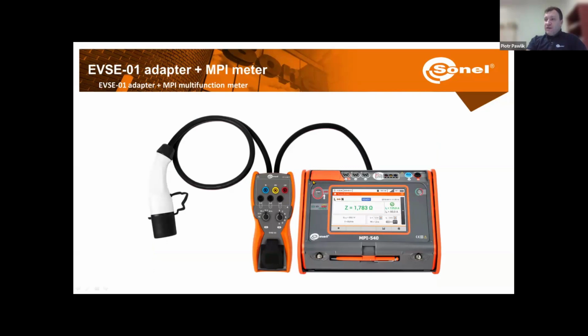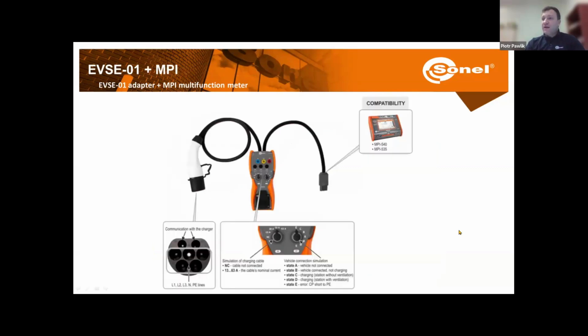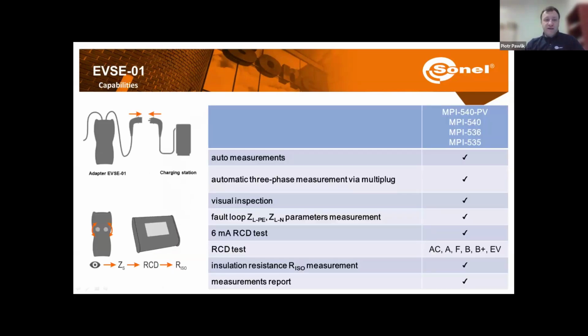Okay, the next solution is the EVSE01 adapter that we can use with our multifunction meters of the MPI series. The adapter is just the interface between the type 2 connector and the meter. Of course, the measurements here depend on the capabilities of the meters, but we recommend the MPI 535, 536, 540 or 540 PV, because we can check the RCDs and RCMs in the charging stations.